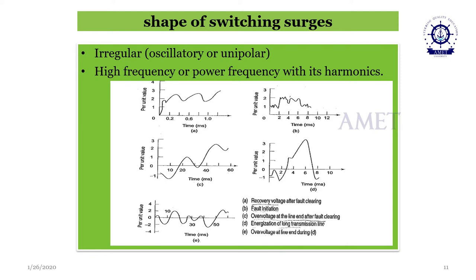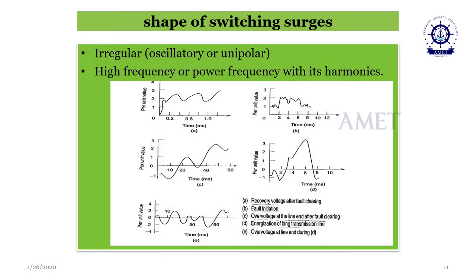By man-made actions or switching actions, these types of transients or surges are created in the electrical power system. Their characteristics are very peculiar compared to other types of waveforms. They are basically irregular, they don't have any proper shape, and they carry high frequency harmonics. Since these waves are generated due to man-made actions, high frequency harmonics are injected, and the wave is shapeless, and sometimes it could be of oscillatory type or of unipolar type.